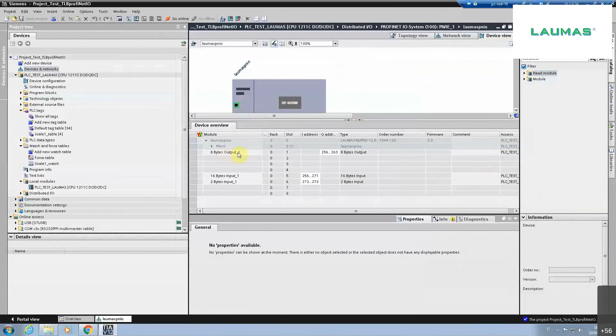With a double click on the TLB symbol, we have access to other important information. More precisely, we are able to see how the data exchanged between the TLB and the PLC are organized and addressed by the PLC itself. Here we see that a group of 8 bytes has been set in the output area, corresponding to the data cyclically sent by the PLC to the device during the communication, starting at address 256. In the same way, we see a group of 16 bytes defined in the input area, corresponding to the data cyclically received by the PLC. This group also starts at address 256.